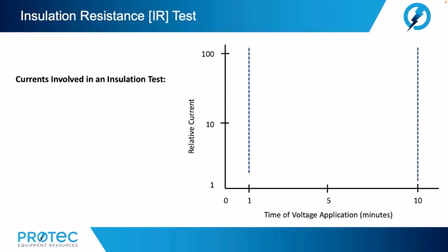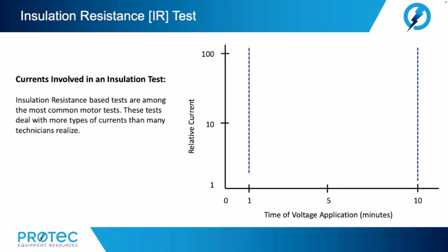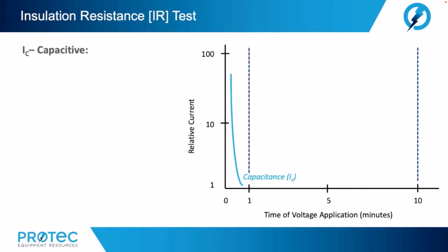Hey, but before we move on any further, let's talk about the currents that are involved in an insulation test. Insulation resistance-based tests are among the most common motor tests, and these tests deal with more types of current than many technicians realize. The currents involved in an insulation resistance test are the capacitive current.